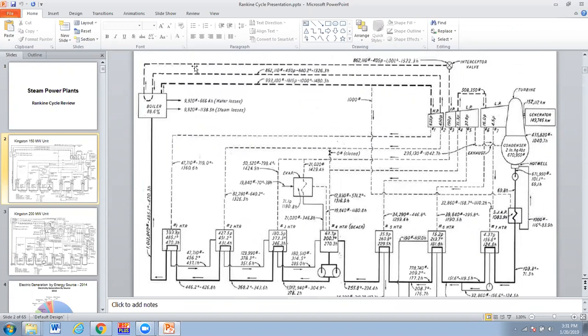The reheat steam flows back into the boiler through the reheat tubes, picking up temperature. It enters at 640.2°F and gets boosted back to 1,000 degrees, but the pressure has dropped 40 PSI — from 450 to 405 PSIA. This is real cycle behavior; you flow steam through long pipes and tubes to reheat it in the boiler and you get some real pressure loss. That's what really happens in the world, not the ideal problems from thermo class.